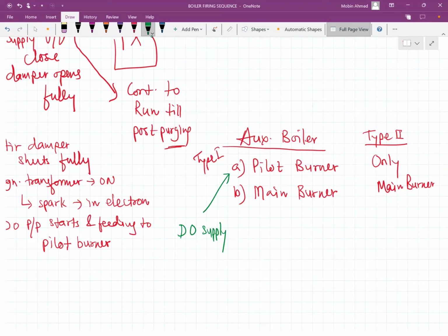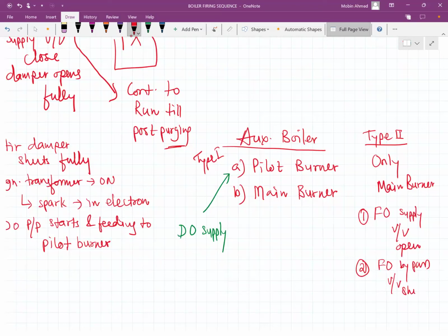In the type 2 condition, where only the main burner is there, in that case, your FO supply valve, this will open - it is not going to open fully, but it will open. So there are some other systems where only the main burners are there, and the FO bypass valve will shut, this is going to shut.